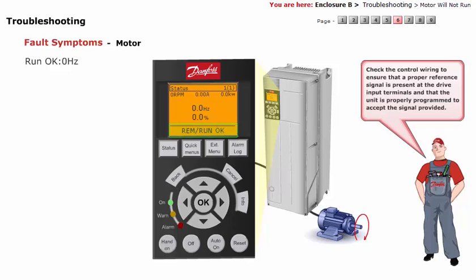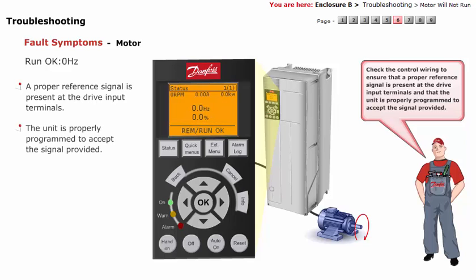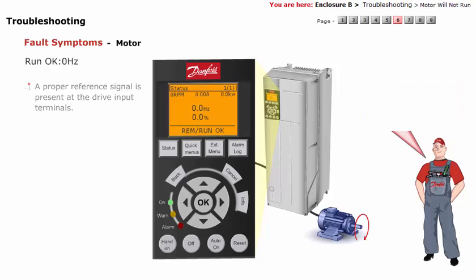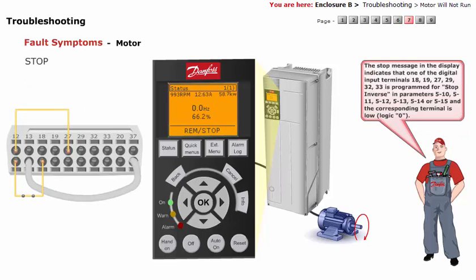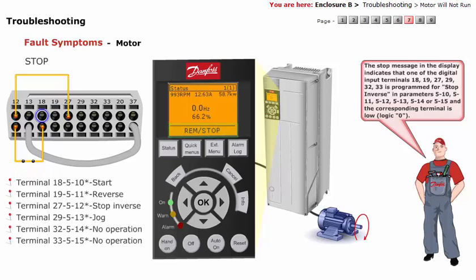Check the control wiring to ensure that a proper reference signal is present at the drive input terminals and that the unit is properly programmed to accept the signal provided. Stop: the stop message in the display indicates that one of the digital input terminals 18, 19, 27, 29, 32, or 33 is programmed for stop inverse in parameters 510, 511, 512, 513, 514, or 515, and the corresponding terminal is low — logic 0.